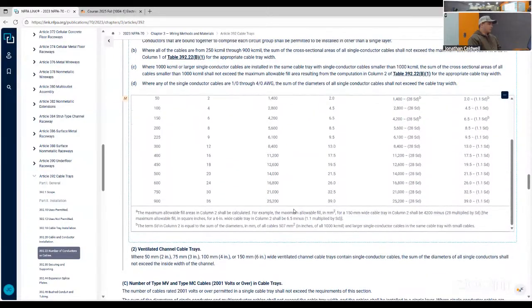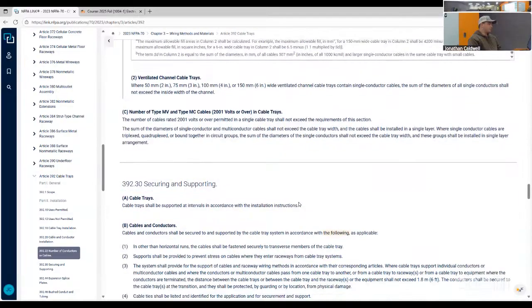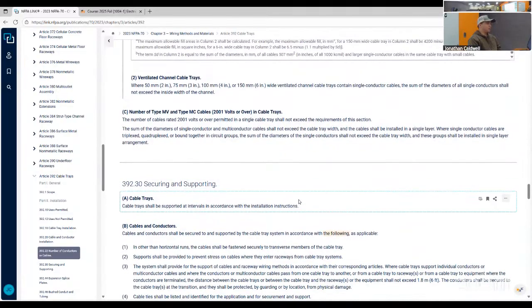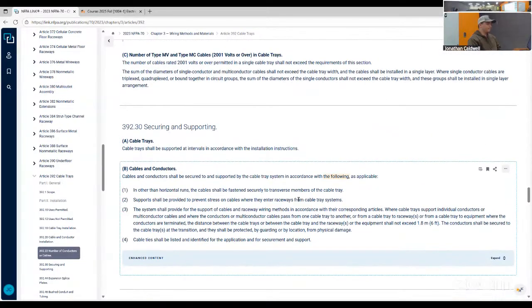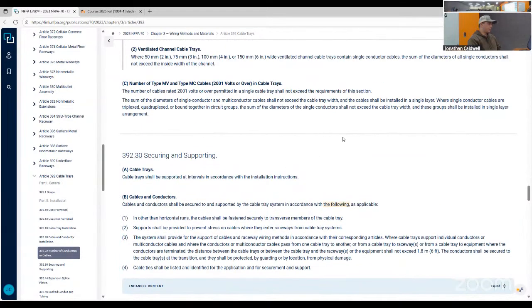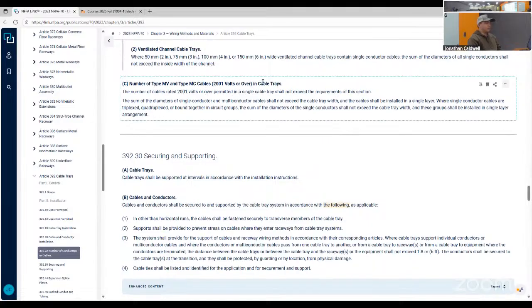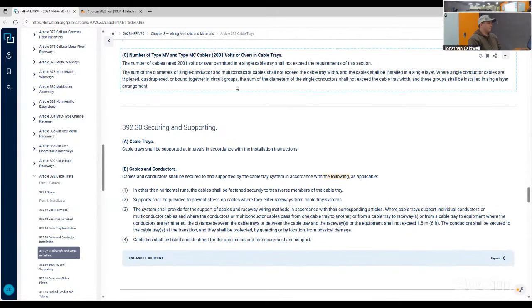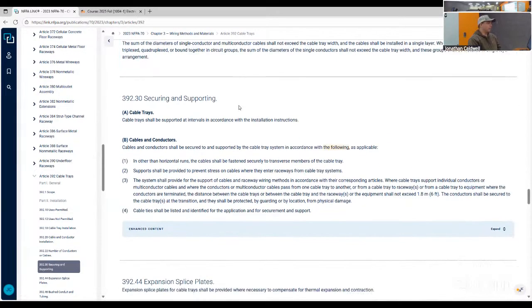Then this is the number of single conductors in a tray, ventilated channel cable tray types, and the number of medium voltage and MC cables, 2000 volts and higher. We do deal with medium voltage out there. I'm sure everyone that has worked out there has had a hand in it. But the medium voltage we deal with is 4160. Obviously, Idaho Power coming in is gonna be way higher, but that's what we deal with. But that's always gonna be engineered, so don't even worry about doing any of that.